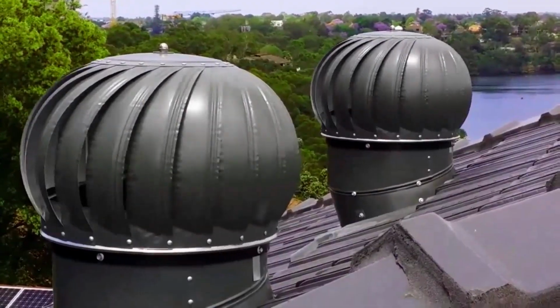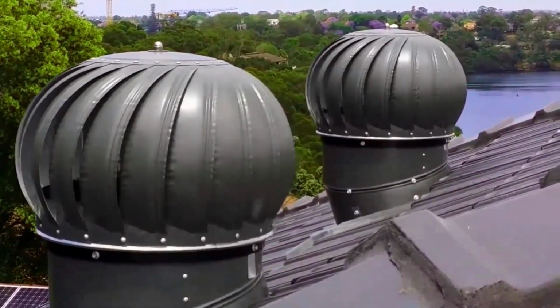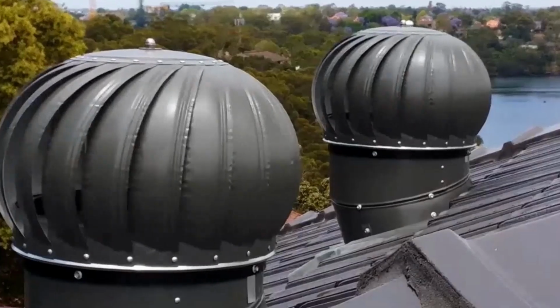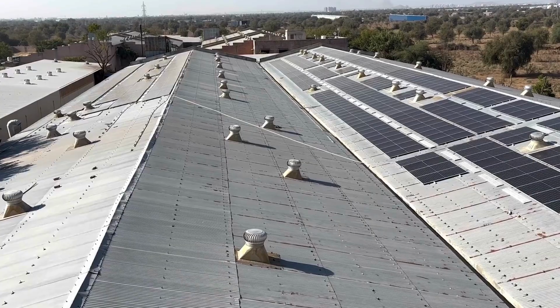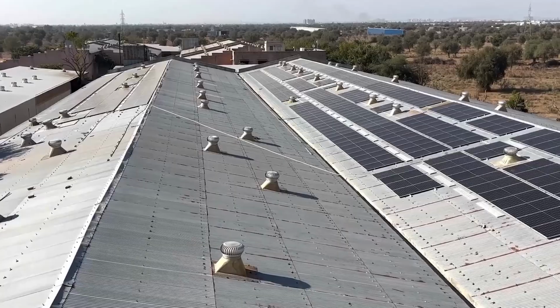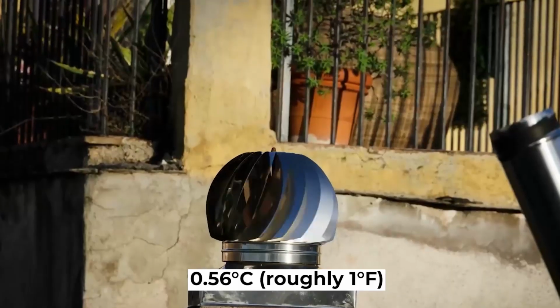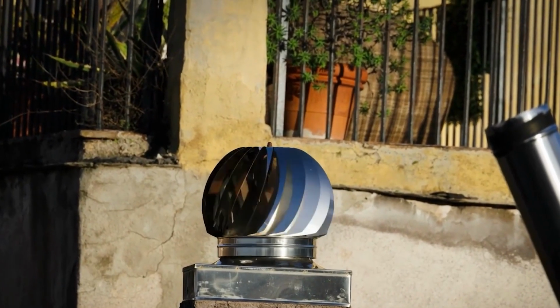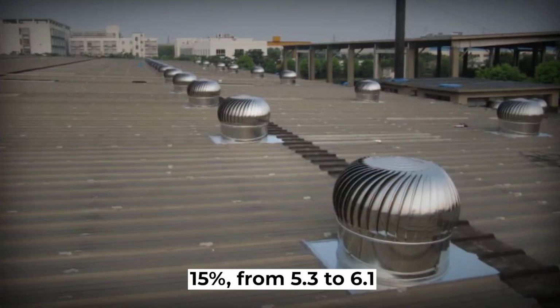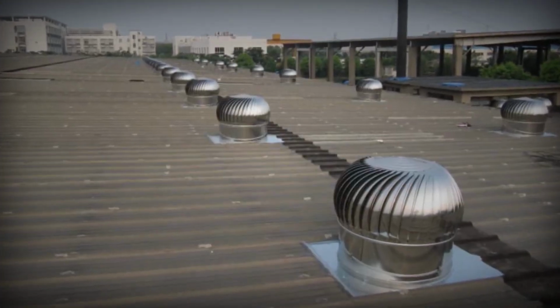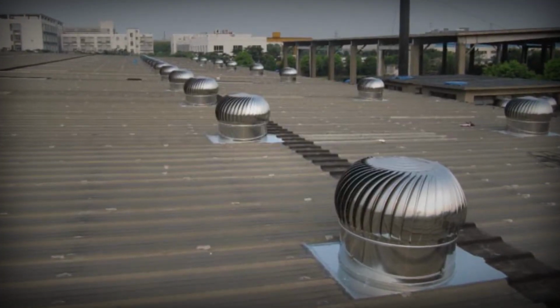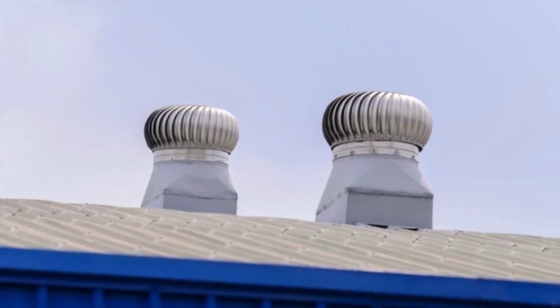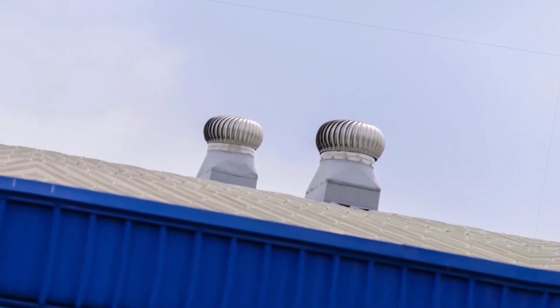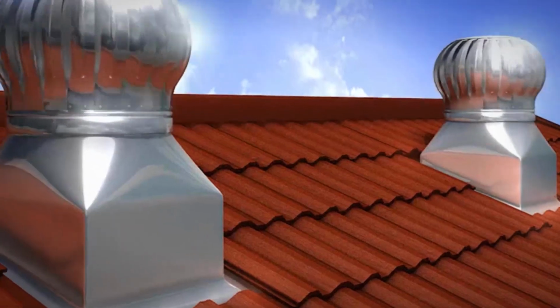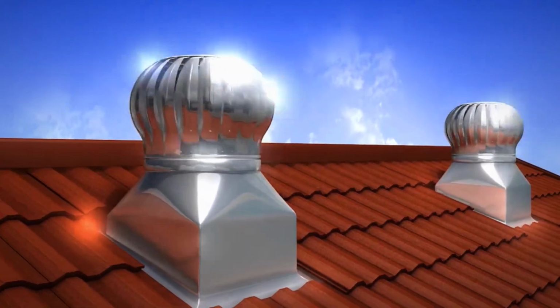A comprehensive review of rooftop turbine ventilator research published on ResearchGate, "Rooftop Turbine Ventilator, a review and update," found that in U.S. temperate climate and windy conditions, the turbine ventilator could reduce attic temperature by approximately 0.56 C, roughly 1 F, and increased ventilation rates by 15%, from 5.3 to 6.1 air changes per hour on average, citing the foundational study by Dale and Ackerman, published in ASHRAE Transactions 1993. This is a modest direct temperature reduction, and the script you may have seen claiming 30 F or larger numbers from a passive turbine is not supported by peer-reviewed data.